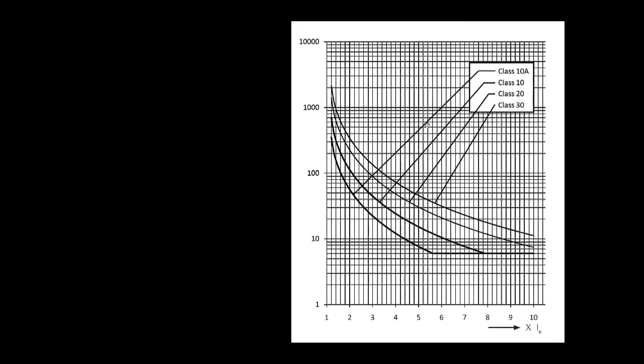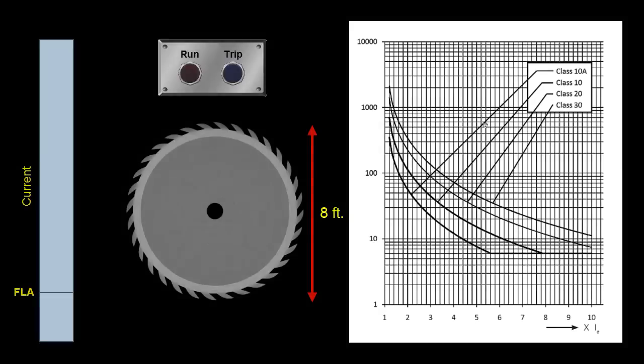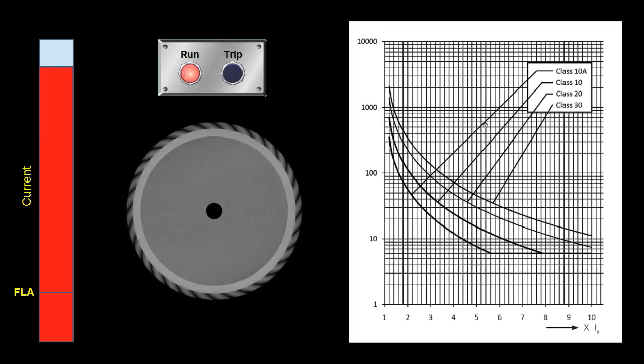For example, let's take a look at this industrial saw that has an 8-foot diameter, which could take several seconds to get up to speed. It not only has a high inrush to get it going initially, but it's also going to pull several times the FLA for the entire duration of startup.